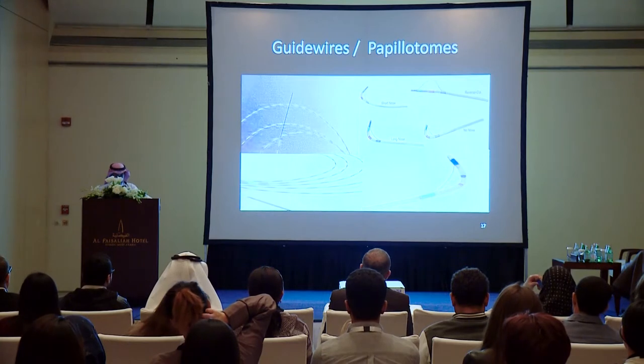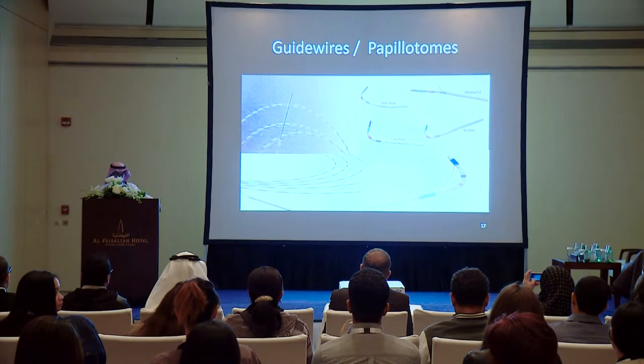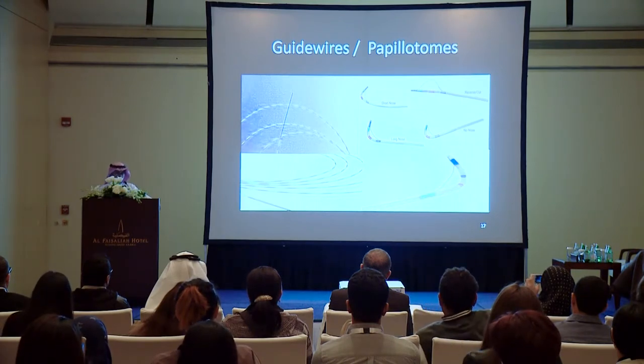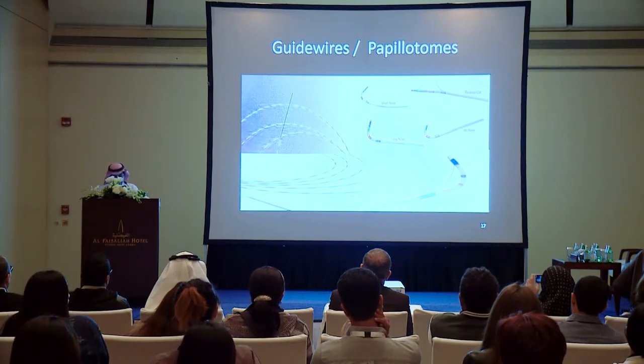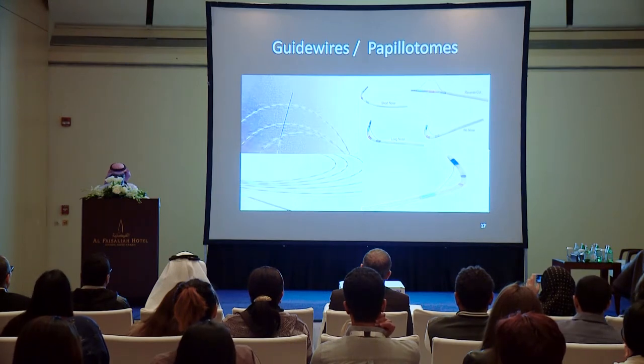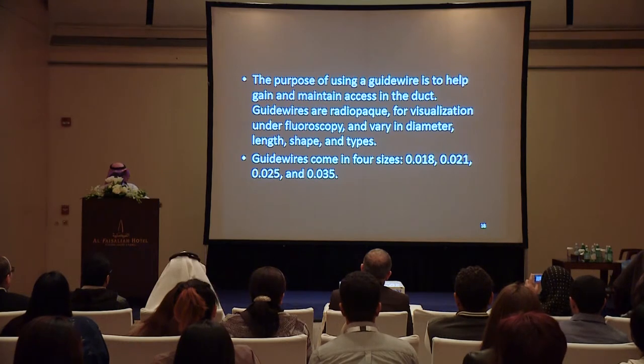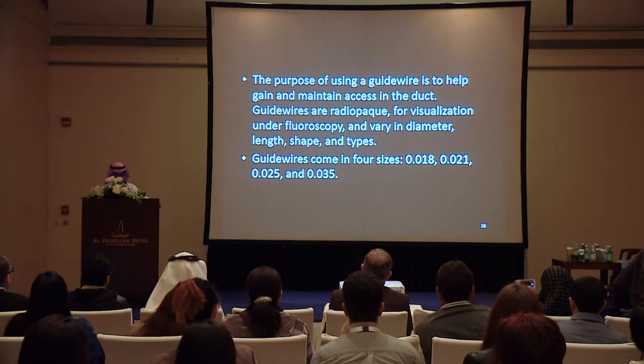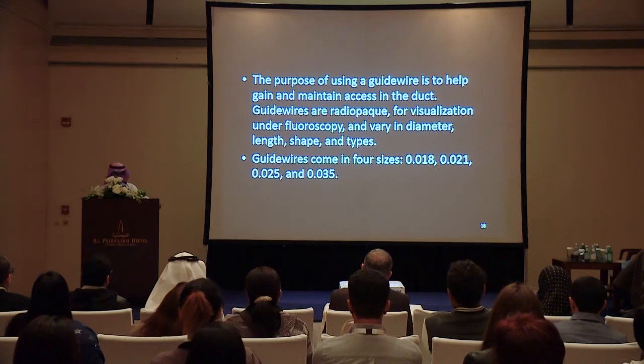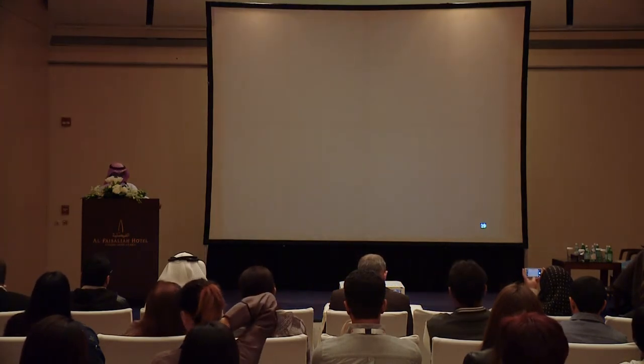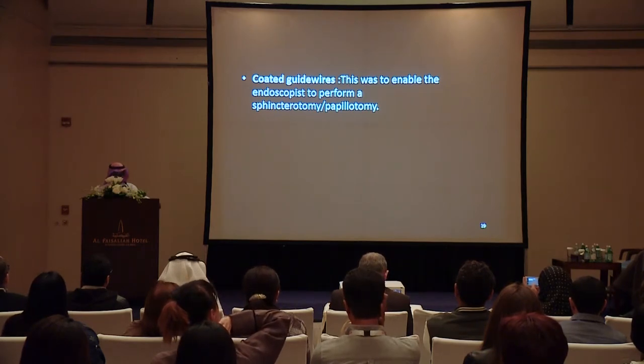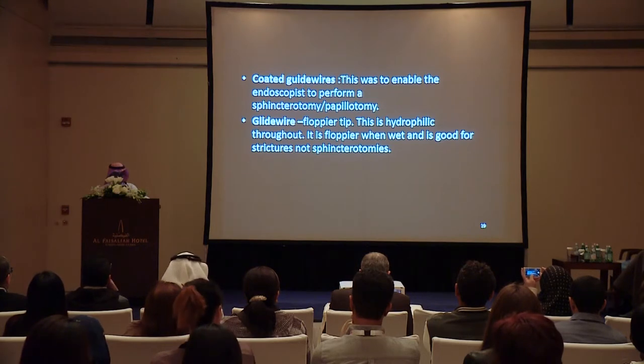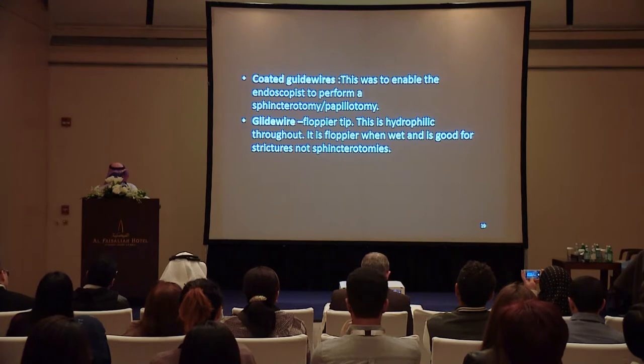There are many guide wires available on the market, and based on physician preference and hospital availability, you select accordingly. The purpose of using a guide wire is to help gain and maintain access to the bile duct. Guide wires are radiopaque, visualized under fluoroscopy, and come in varying diameter, length, shape, and type — in four sizes: 0.018, 0.021, 0.025, and 0.035. The coated guide wire enables the endoscopist to perform sphincterotomy. The glide wire has a floppy hydrophilic tip — it is slippery when wet and good for strictures, not sphincterotomy.